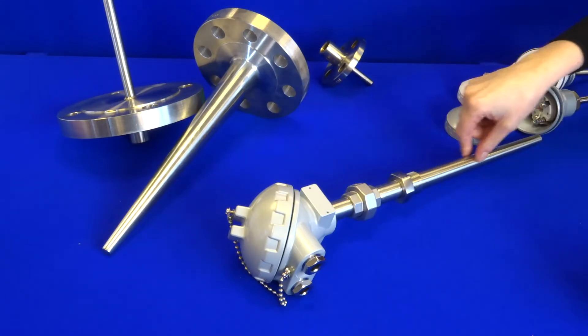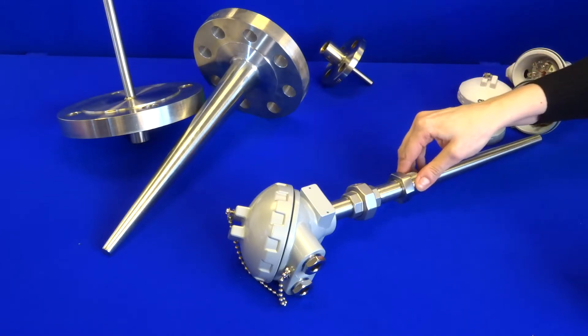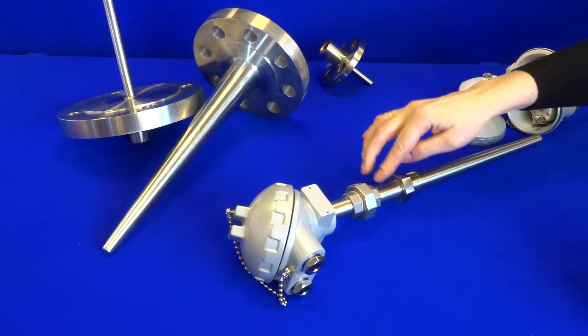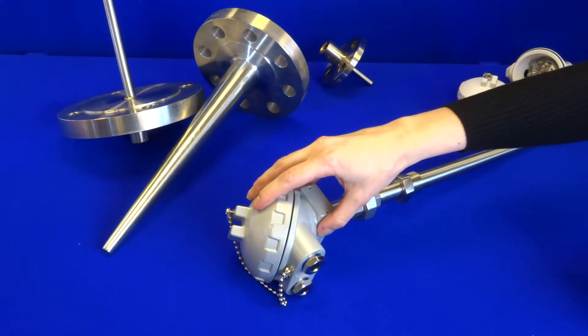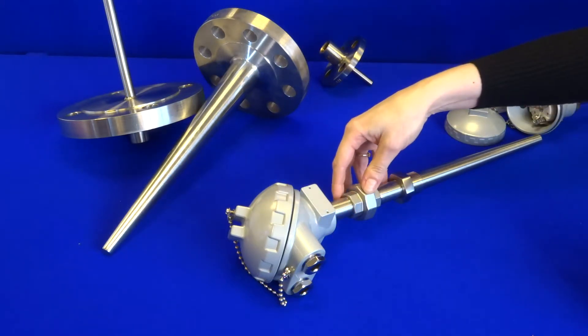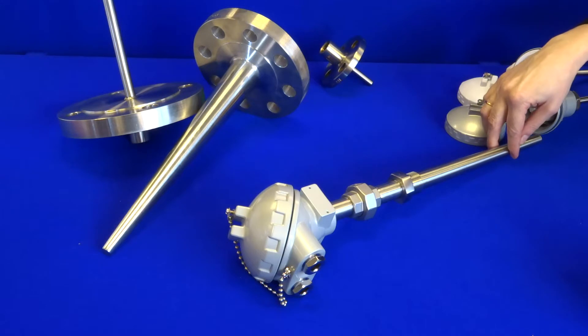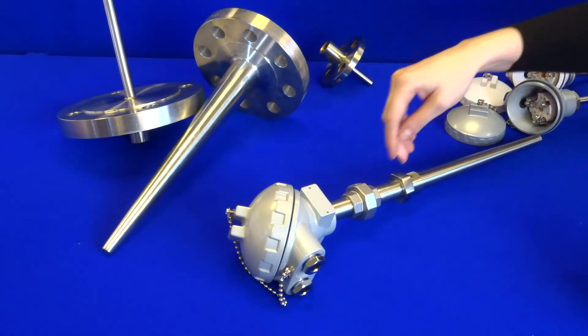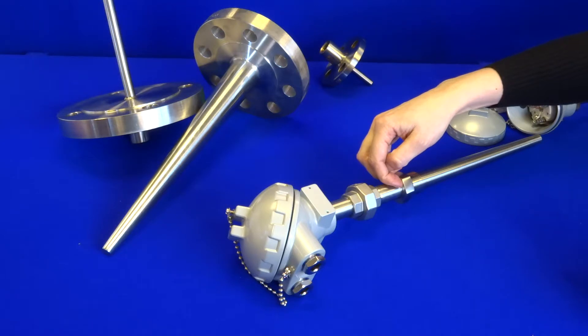This particular version has a solid drilled tapered stem, it has a screwed thread, nipple union, nipple connection and a die cast aluminium industrial head. With regards to the union connections, this allows you to move the head in any orientation without disturbing the pocket itself, and you're also able to manipulate the length whilst installing.